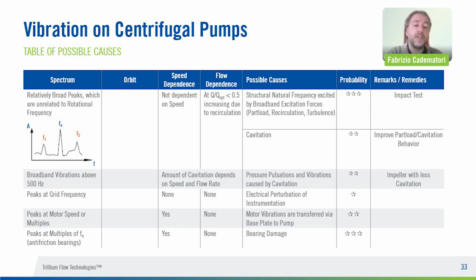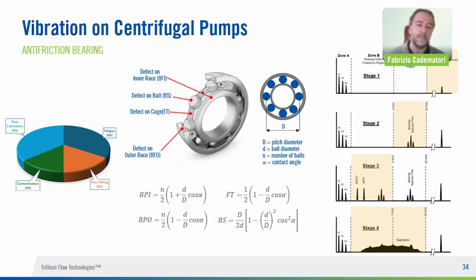And regarding cavitation, normally it creates a random high frequency vibration or noise. And our last phenomena in the map are peaked grid frequency related to electrical perturbation, peak at motor speed that could be transmitted via base plate to the pump, and anti-friction bearing issues that I will explain better in the next slide. Next slide, please. Okay. Anti-friction bearings have different damage stages, and to understand them, we must use different techniques.